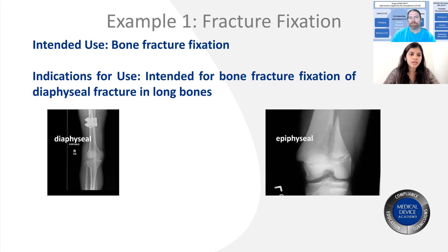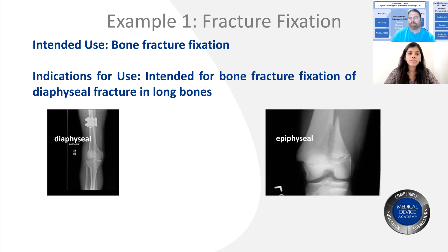On the left side we have an image of a diaphyseal fracture, and on the right side a picture of an epiphyseal fracture, which is at the end of the bone — diaphyseal being in the middle of the long bone. In the indications for use, they have specified that it is intended for bone fracture fixation of diaphyseal fractures in long bones. So it is only going to be used for the middle of the long bone. That is the difference between intended use and indications for use — indications give more detail about where it will be used, while intended use is just a broad idea of what the device is used for.